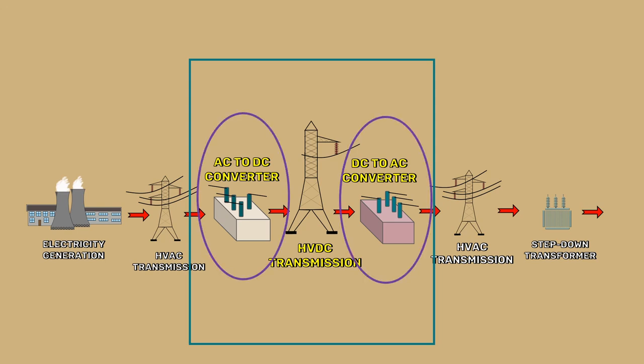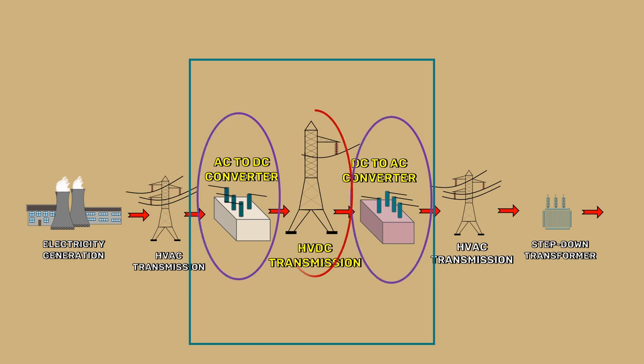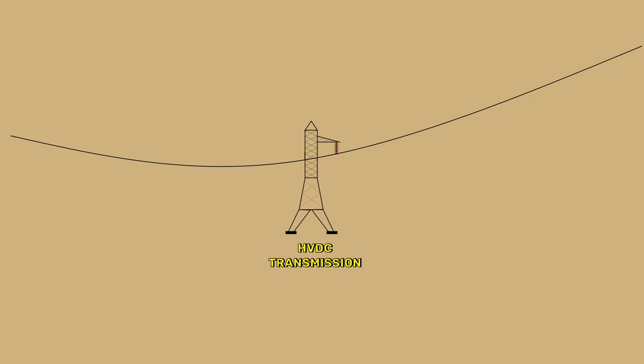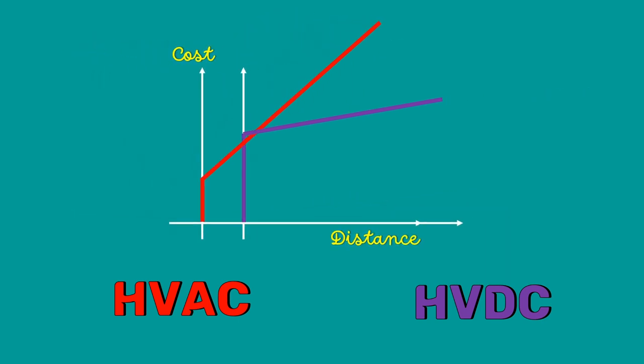However, the cost of the terminal equipment of HVDC is very high — these semiconductor converters are very expensive. The overall cost of transmission depends on both the terminal equipment cost and the transmission line cost. The terminal equipment cost is fixed, but the transmission line cost increases with distance. On a cost-versus-distance graph, the terminal equipment cost of HVDC is higher than HVAC, while the transmission line cost of HVDC is lower than HVAC.